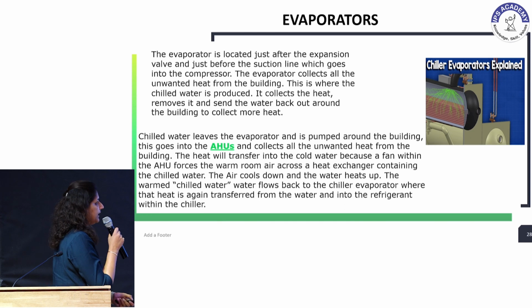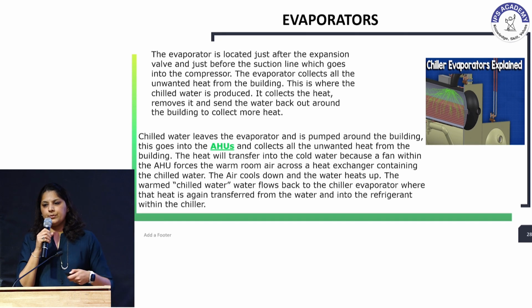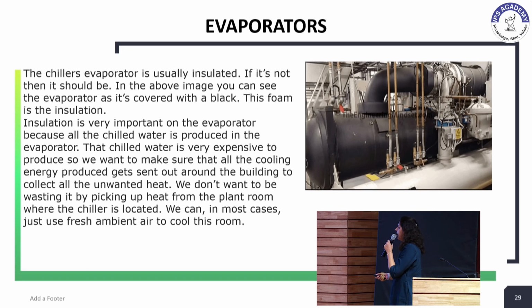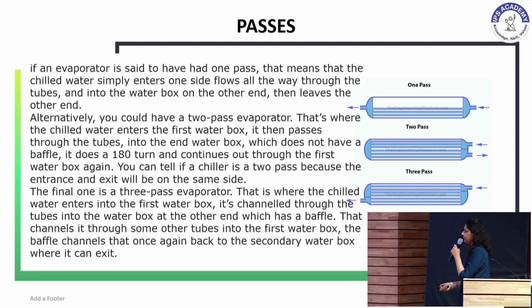So we come to evaporators now. There are different types of evaporators. Specifically, when we talk about the way you want to evaporate inside your machine, it just defines how efficient you want your machines to be. So the evaporators can be DX. In DX evaporators, normally the refrigerant is in the tube and the water is in the shell, so less refrigerant is used to evaporate the refrigerant which passes in the evaporator. And in flooded type of evaporators, the refrigerant is in the shell and the water is in the tube, so a higher quantity of refrigerant is required in flooded evaporators. The evaporators again can be single pass, two pass, or three pass, on the basis of the design in which you want to route your refrigerant cycle.